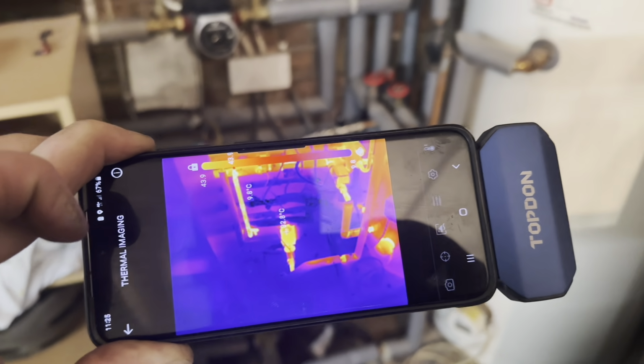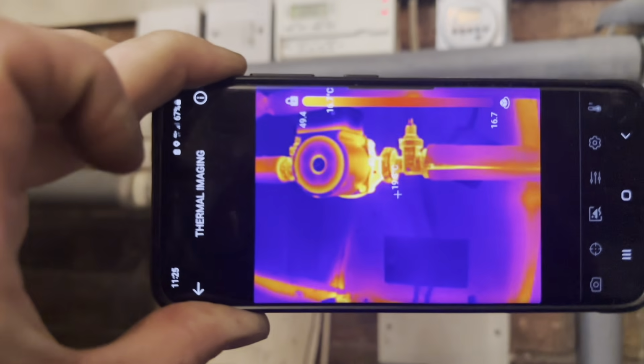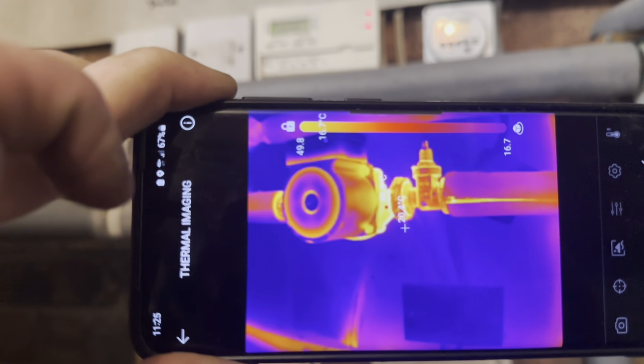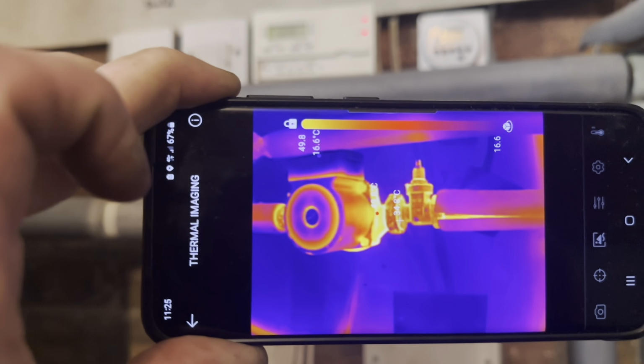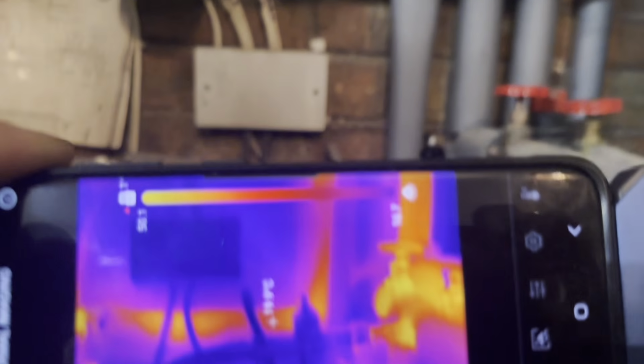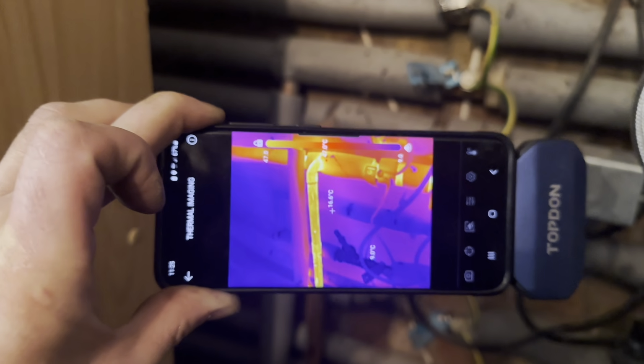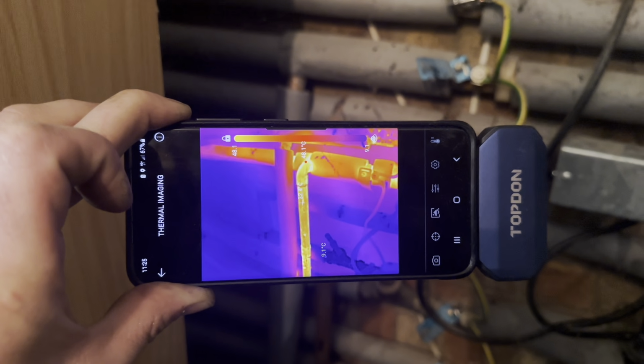It's drawing 32 degrees round from my hot off the cylinder. But what I'm looking for is my flow on my pump. I've got there a nice 49 degrees. You can see at the back, brass fittings out is a little cooler. And then she's going around and I'm looking for my flow pipe there, which is great, that's at 34. So I'm hoping now this is going to eliminate a lot of it.